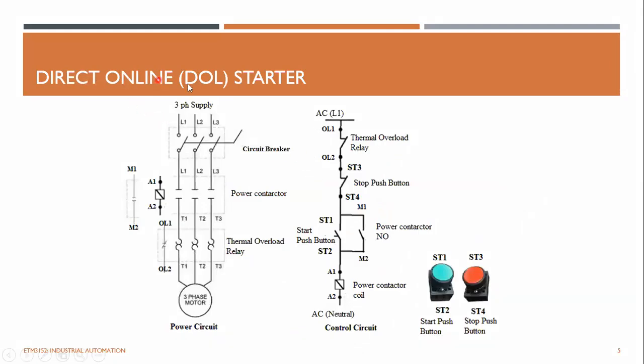So this is a direct online starter wiring diagram. This is the circuit breaker. You can see three-phase supply is fed, and this is your three-phase motor. Once you want to turn it on, you can just press it. So all the three contacts here get closed, and the power is coming from here. And this is your main contactor, right? So it has a coil like a relay. Once this coil is energized, these three contacts get closed, and the power can flow from top to bottom.